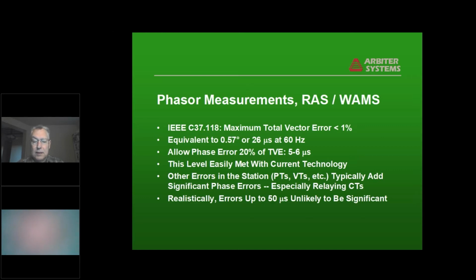And there's other things in the substation that typically add much more in the way of phase and magnitude errors, especially CTs and PTs used for relaying. They have a very high dynamic range, but the normal operating current is way down on the magnetization curve, so that the phase offset tends to be larger than it would be at higher currents. So typically, we can get down to a fraction of a microsecond, which is great, but data is still usable up to as much as 50 microseconds, because that gives you about a 1 degree error, and that's not ideal, but it's still usable.